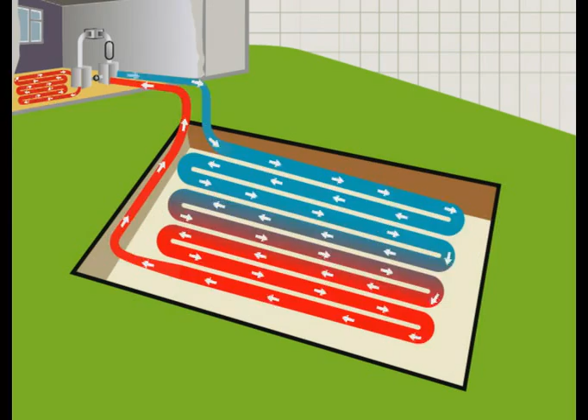So it is happening. OK, let's take a look at how a typical ground source heat pump system works. There are three main components: a ground loop which collects the heat, the heat pump itself, and the building's heat distribution system. The ground loop comprises lengths of pipe buried in the ground, either in a borehole or a horizontal trench. The pipe is usually a closed circuit filled with a mixture of water and antifreeze, which the heat pump circulates, absorbing heat from the ground.